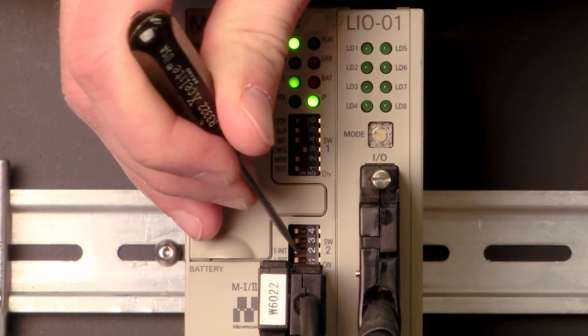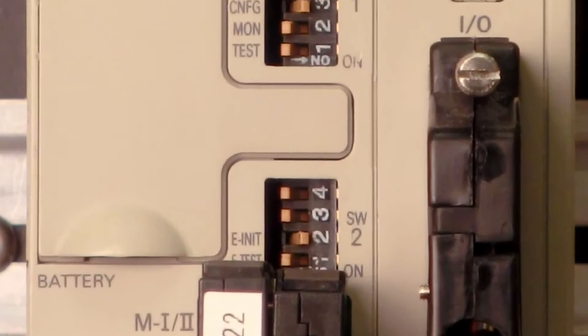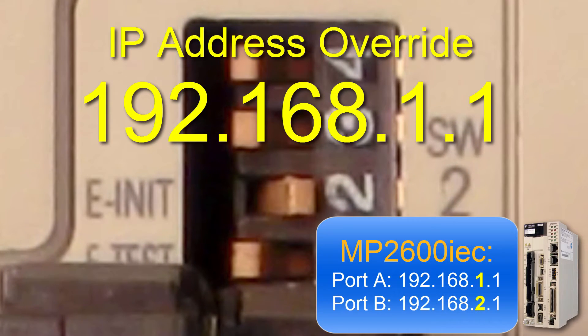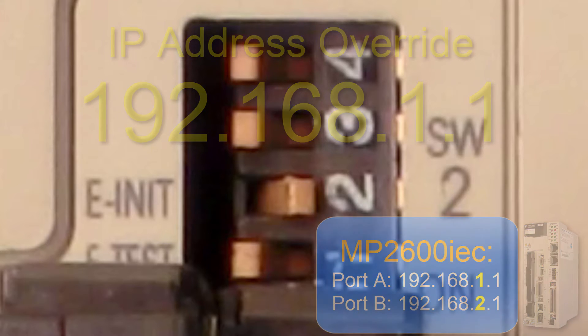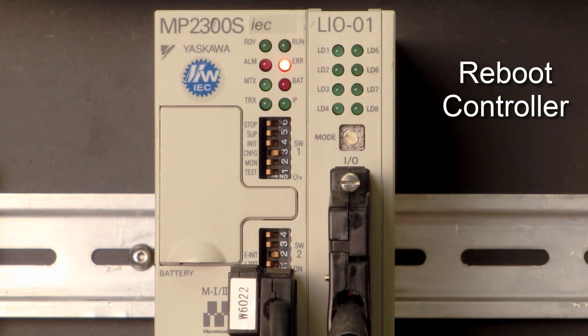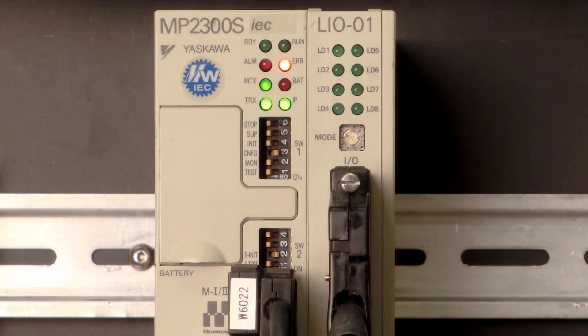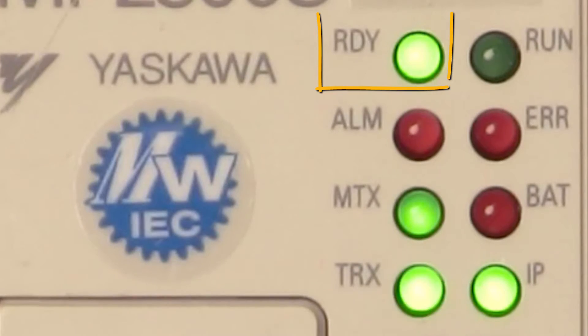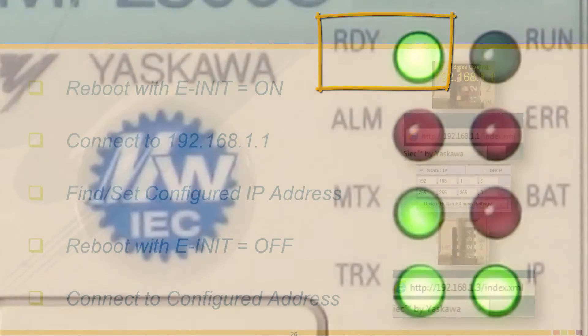Rebooting with the EINIT switch ON temporarily overrides the configured IP address to 192.168.1.1. Do pay attention to the printed location of ON for the switch as this can vary between controller products. I'll cycle power to the controller. The controller is now rebooting and after about 30 seconds you see the ready light is ON. The alarm light may be ON which is OK.